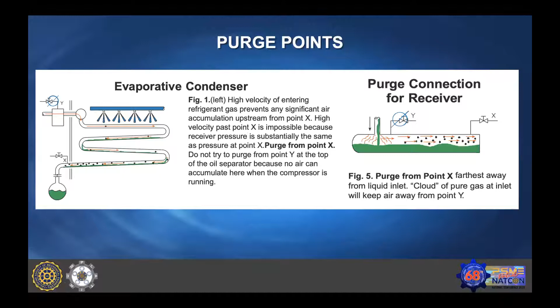Always remember, if you are trying to take a purge point from here and you have even 10% of air, the velocity of ammonia and air is the same. So if your purge point is here, 90% of ammonia will come out even if there is 10% of air. So your purger will always be filled with ammonia. So these purge points are very, very critical, and a proper purge point decides totally the functioning of the air purger.